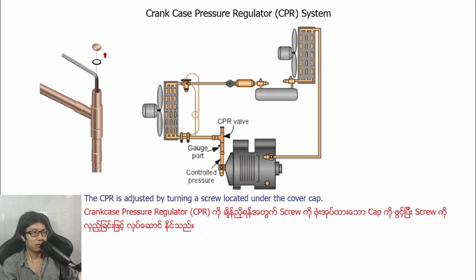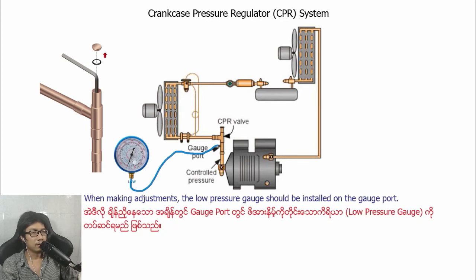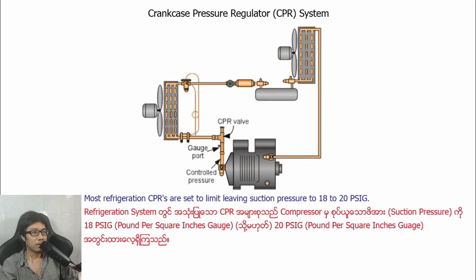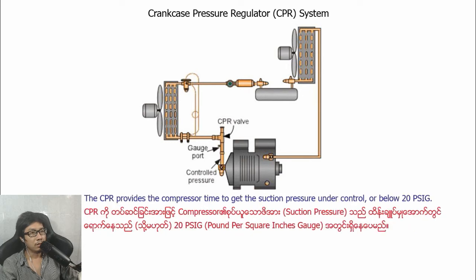Crankcase pressure regulator CPR system. The CPR is adjusted by turning a screw located under the cover cap. When making adjustments, the low pressure gauge should be installed on the gauge port. Most refrigeration CPRs are set to limit leaving suction pressure to 18 to 20 psi. The CPR gives the compressor time to get the suction pressure under control, below 20 psi.